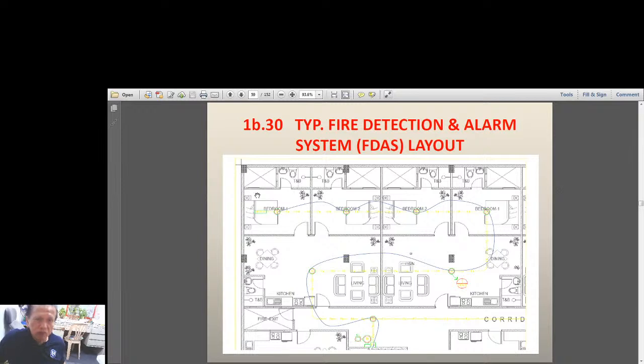So you have here a layout of a floor plan. And you have here rooms. So this is one room, a bedroom, bedroom, bedroom, bedroom. So there are two units, two bedrooms here, and there is this sala. This is the living room and a dining and kitchen area, and two bedrooms. And then you would have smoke detectors interconnecting this, here, here. All of these circles are smoke detectors. This one, this one, and this one, and this one, and of course, this green symbol here is the fire alarm control panel, and you will see a buzzer here, a bell and a buzzer to initiate the alarm.